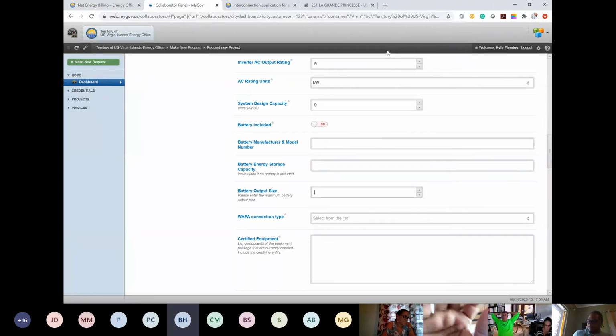So what are we going to call that? Are we going to try to make a computation, or are we just going to use the 20 or 24-hour amp hour rate of the battery bank? I would recommend we just use either the 20 or 24-hour amp hour capacity of the battery, because trying to figure out how many kilowatt hours that amounts to involves a calculation using the battery's nominal voltage, or a lower or higher voltage.